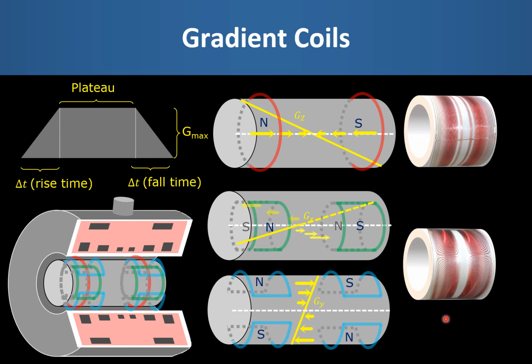We also need very high power amplifiers to generate the gradient pulses, and we are typically looking for amplifier power on the order of 1 to 3 megawatts. We need very high voltages to overcome the back EMF in switching on the gradient, so that the rise time is as short as possible, and relatively high currents in order to maintain high amplitude pulses. The gradient amplifiers and coils generate large amounts of heat, so we need to dissipate somewhere between 25 to 75 kilowatts. So the gradient amplifiers and gradient coils are water cooled. In many cases, the gradient conductors are tubular so that the coolant can travel directly through the windings.